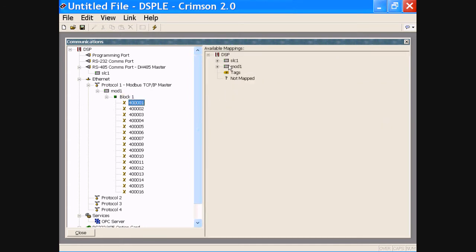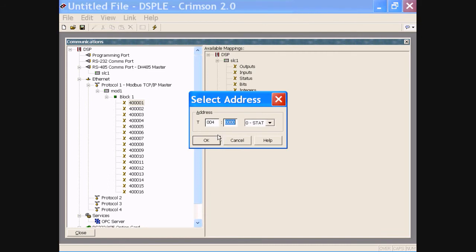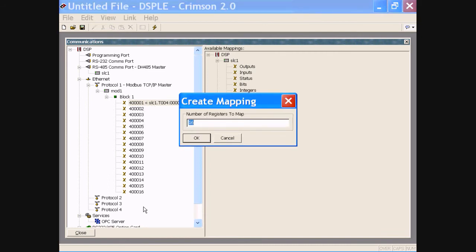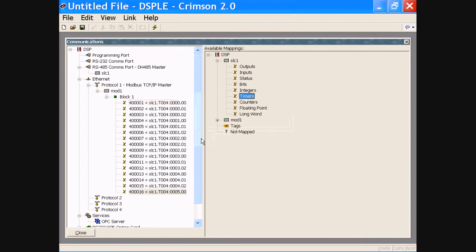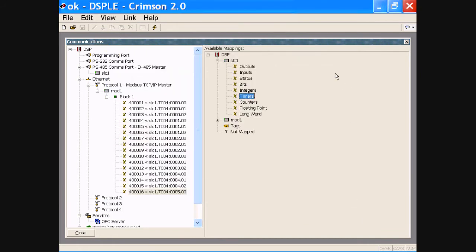Let's go ahead and map in from the SLC — let's say it's timer values. We see the timer. It asks us by default if we want to fill all those registers with timers. Sure, why not? Let's get all 16 SLC timers and map them into the Modicon 40,000 registers. We'll save that. Now if I were connected to the device, we just click this to update it — it downloads the configuration, plug in the PLCs, and they're talking to each other. All the SLC timers would be mapped into the Modicon's 40,000 registers.